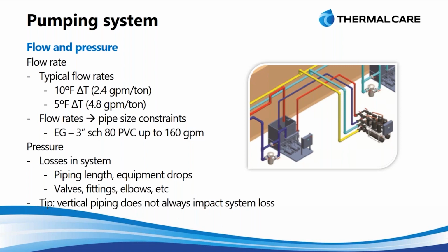One of the things that comes up a lot in questions while discussing, and that a lot of people don't seem to grasp the concept because it's a little foreign and you don't really think about it right away, is that vertical piping loss. Everybody thinks, I'm pumping this up, and so I'm going to be fighting gravity there, so I need to consider extra losses there. But the thing that you need to consider, though, is a lot of times when you pump up, you're actually going to end up pumping back down.